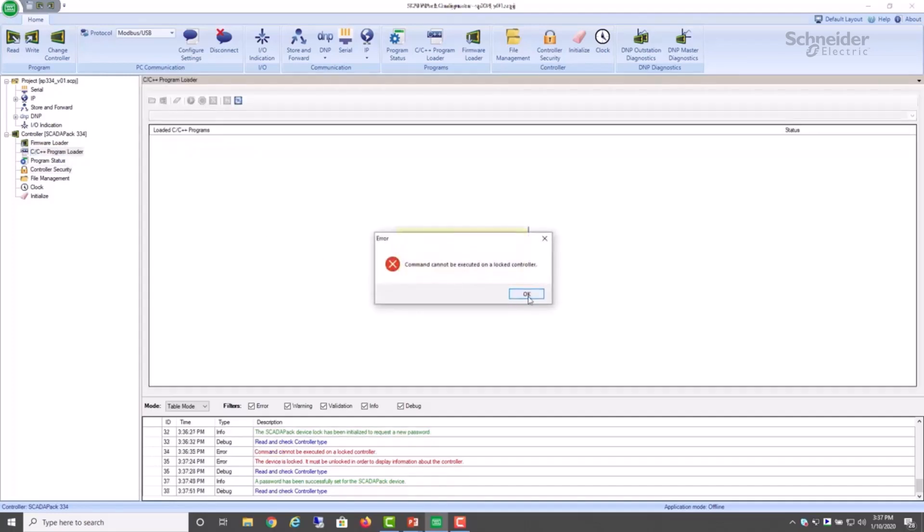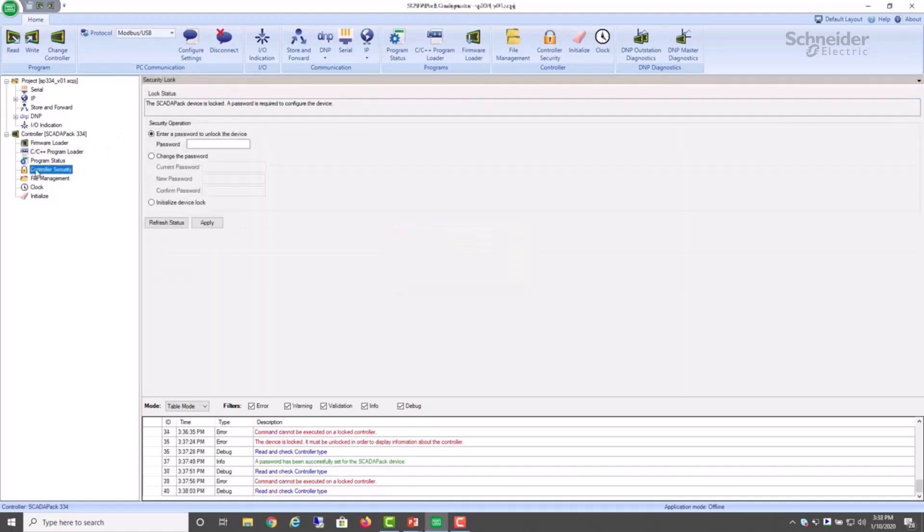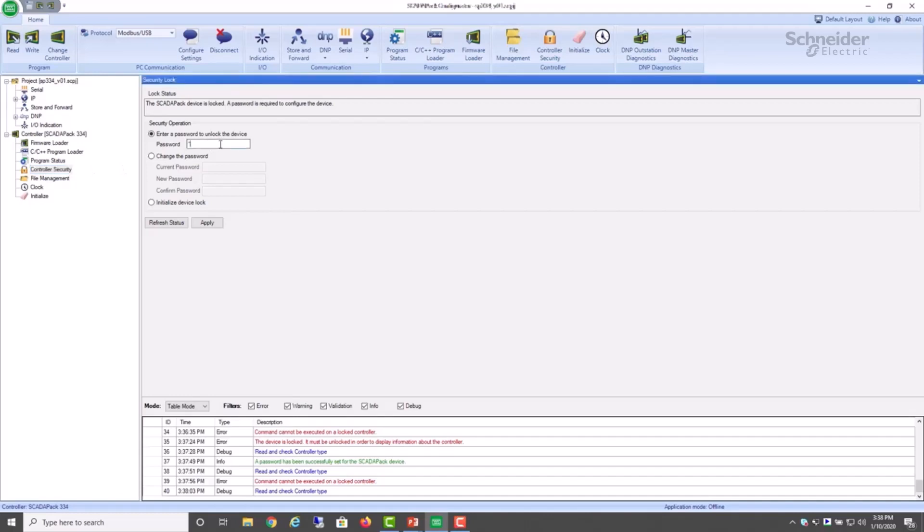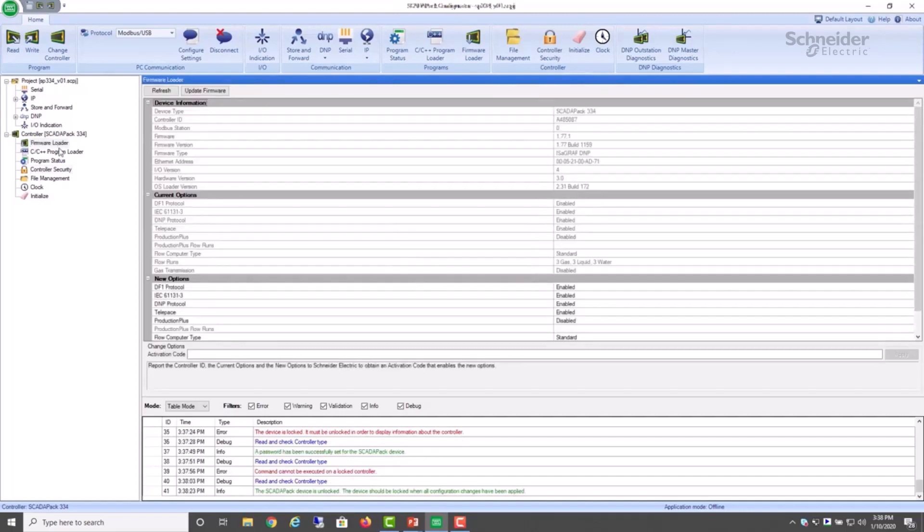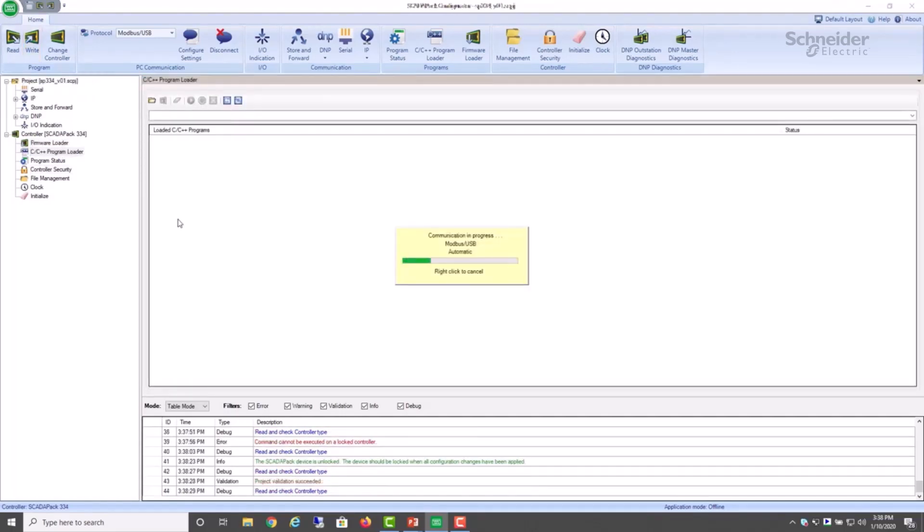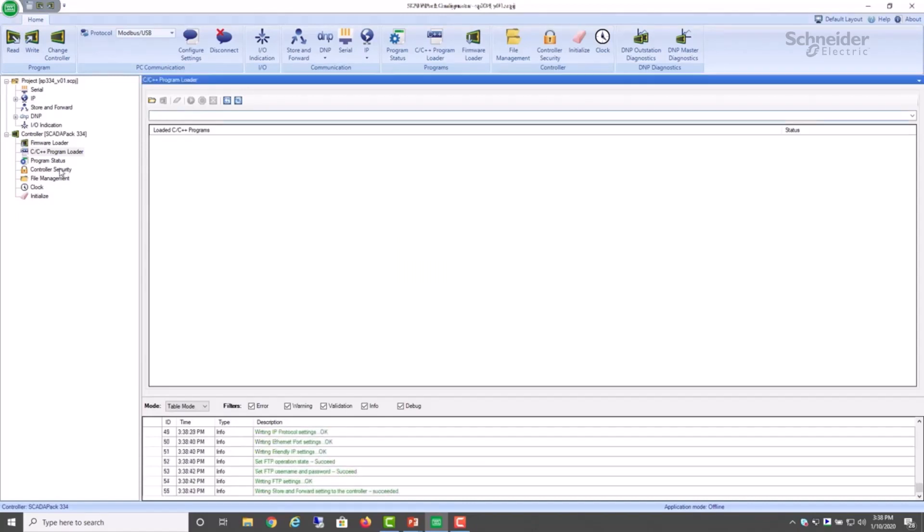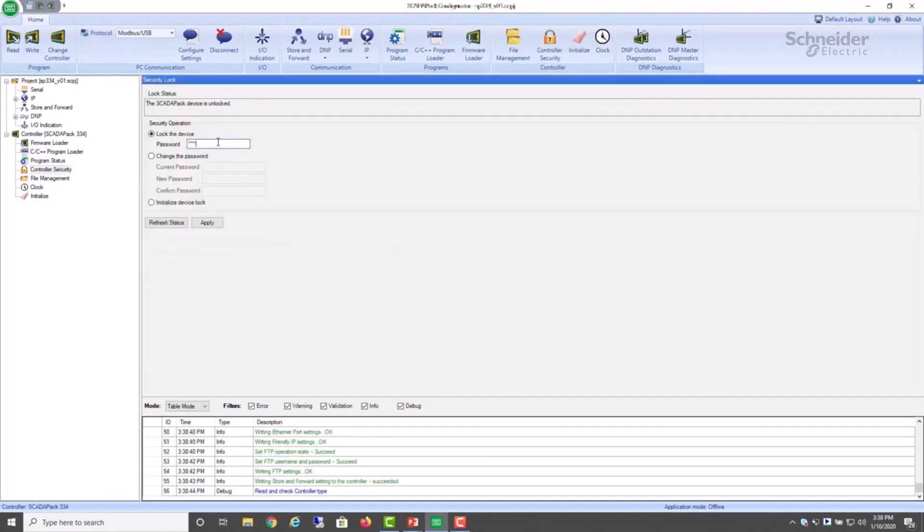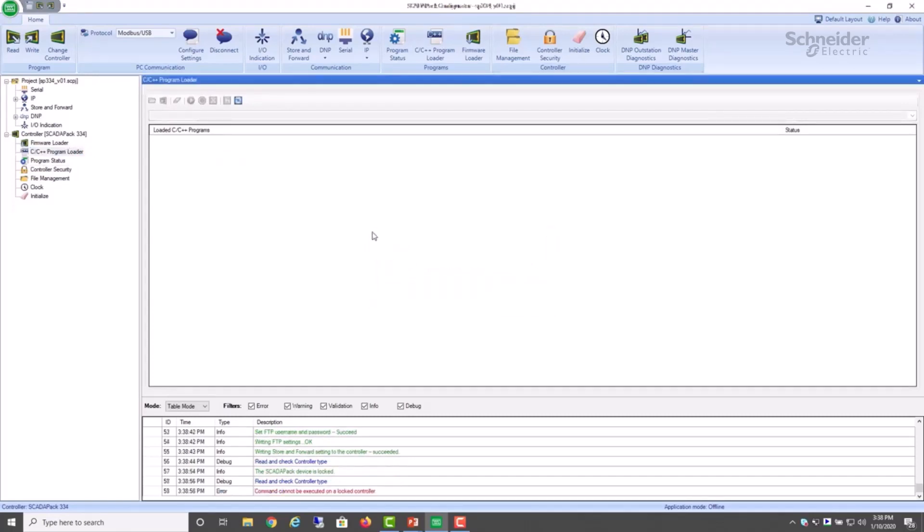So if I select another command, we see that the controller is still locked. But the difference this time is we know the password. So in order to further configure or interact with the SCADA pack, we first have to unlock it. So we go to the controller security dialog again and this time enter the password that we now know. The controller is now unlocked. See the advisory here that the device should be locked after the configuration changes have been applied. So now I'm able to select any command or I can write to the controller. And once I'm finished, I will reapply the lock to secure it. I apply the lock. And now note that no further communication is allowed in configuration.